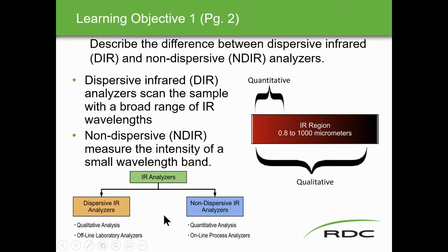When we do this, dispersive infrared does qualitative analysis, and non-dispersive usually does quantitative — how much of that substance. Once we find out what's in it, we find out how much. If we're going to measure CO2 or CO, we pick the infrared analyzer with the proper wavelength of the IR spectrum. Dispersive IR analyzers are offline laboratory analyzers doing qualitative analysis; non-dispersive IR analyzers are quantitative and online process analyzers.